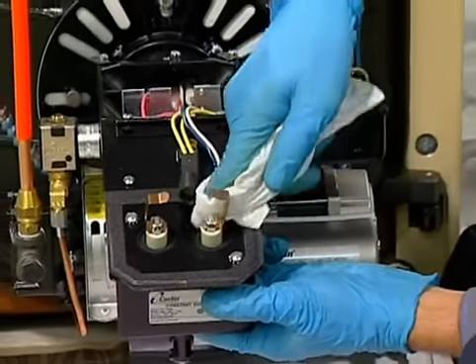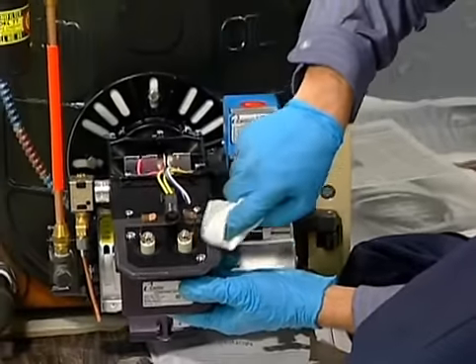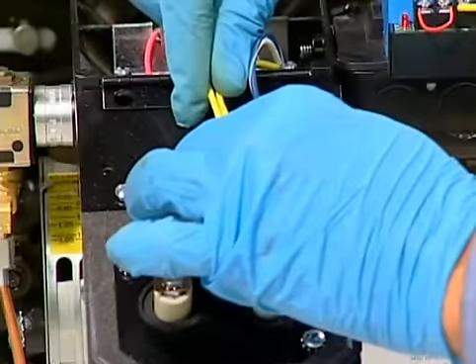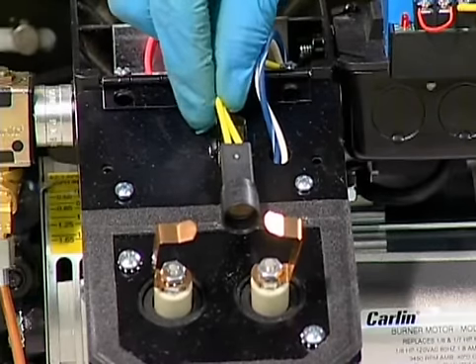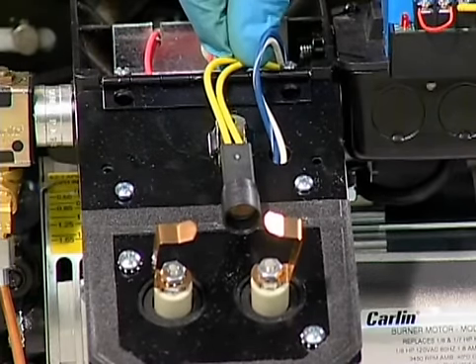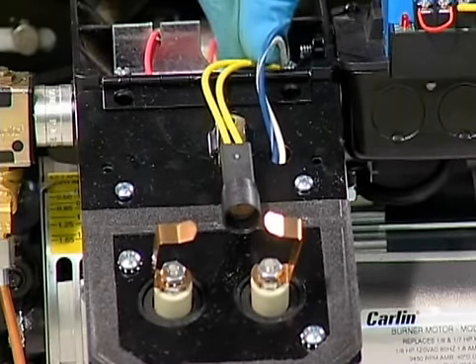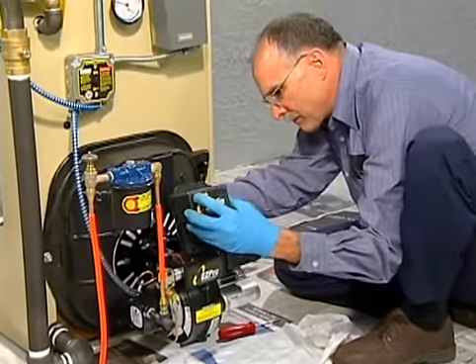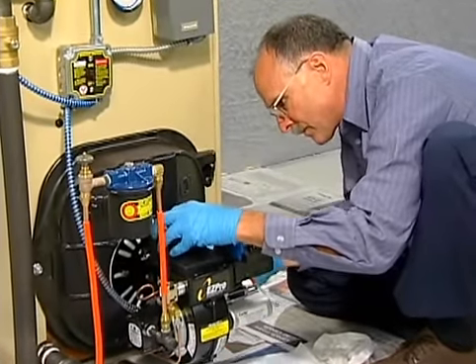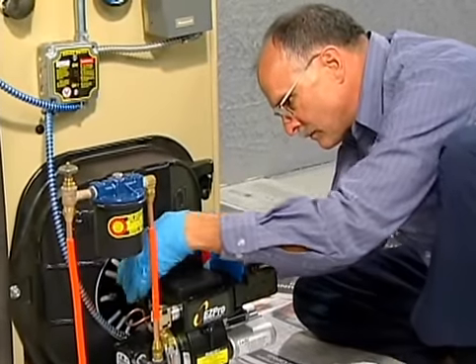Clean and check the transformer bushings and springs. Inspect the ignition wires. Clean the CAD cell eye and check the wires. Make sure the bracket is firmly secured in place and positioned correctly for good flame sighting. As you close the transformer, ensure that the bus bars are making solid contact with the transformer springs.